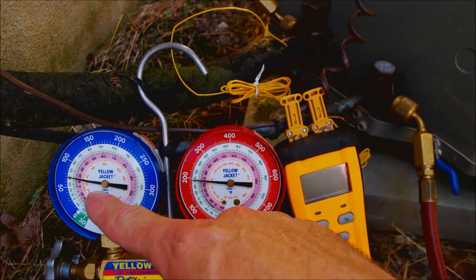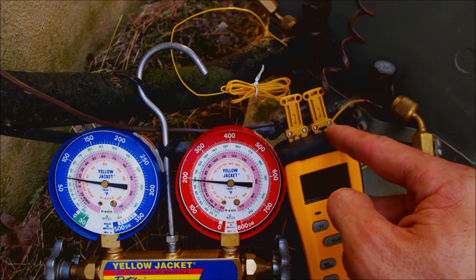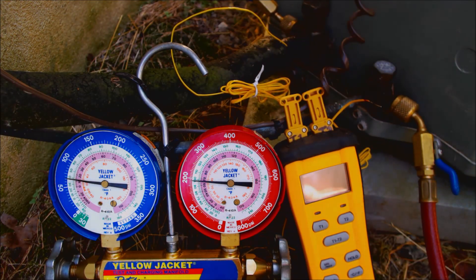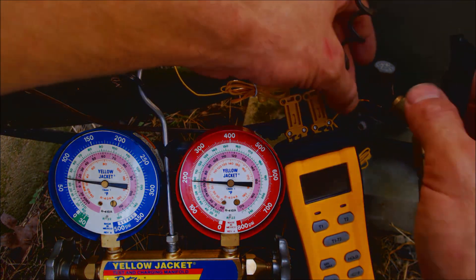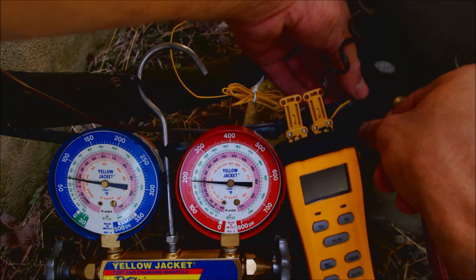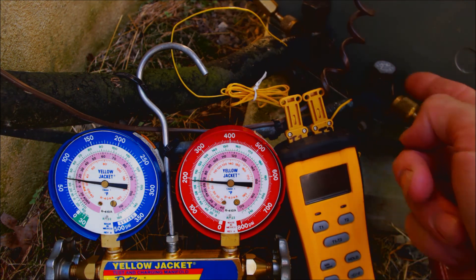Now we're reading our pressures on the low side and the high side. I'm going to tape my T2 sensor right here onto the liquid line, and I have my T1 sensor already taped onto the suction line. You could use clamp style temp sensors, but I prefer these bead type temp sensors — you just tape them right on. Make sure that these sensors are out of the sun and within three inches or so of the service ports.